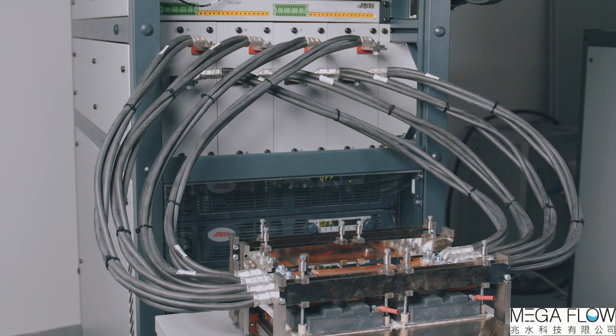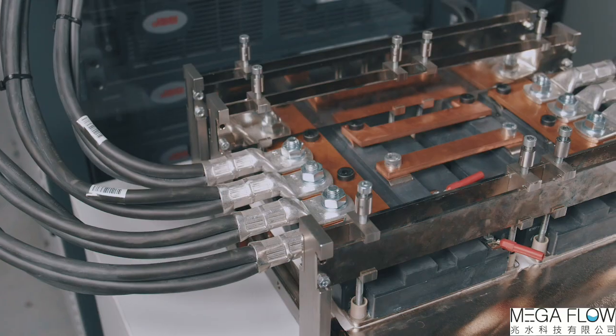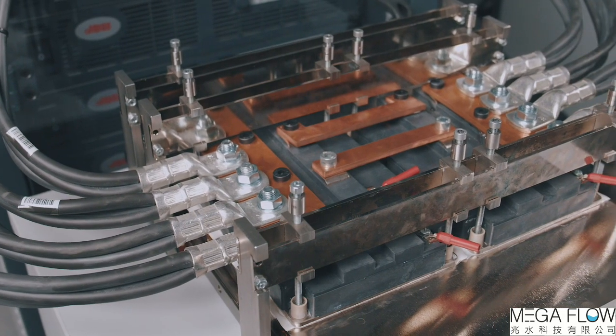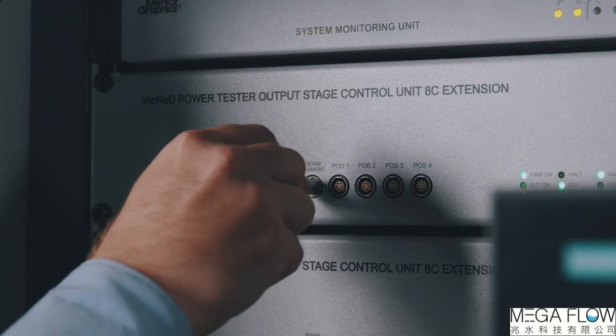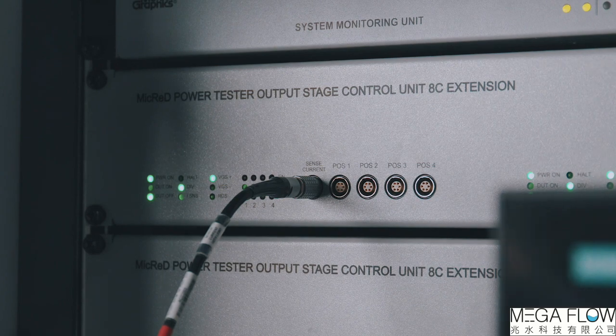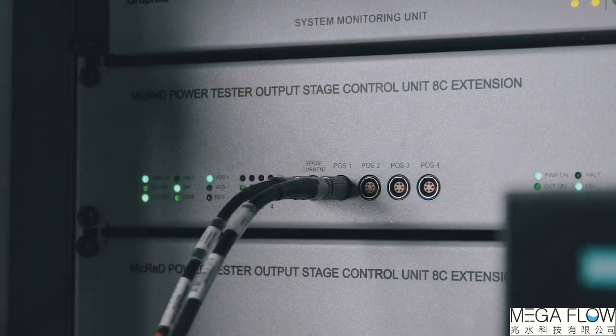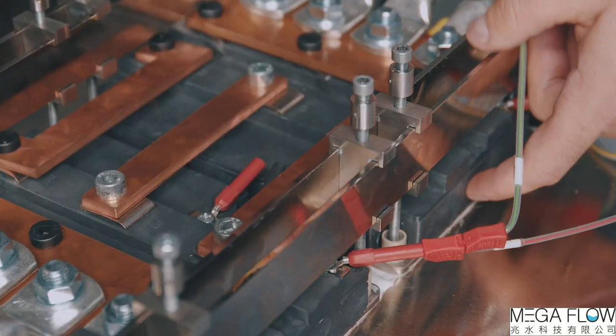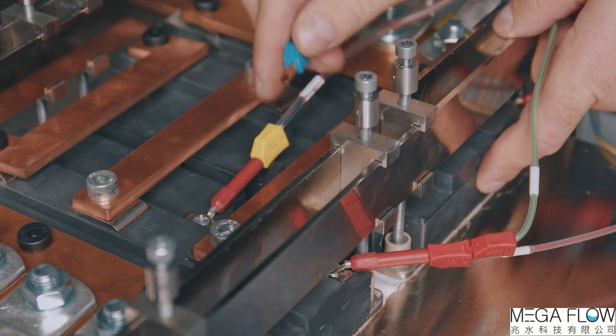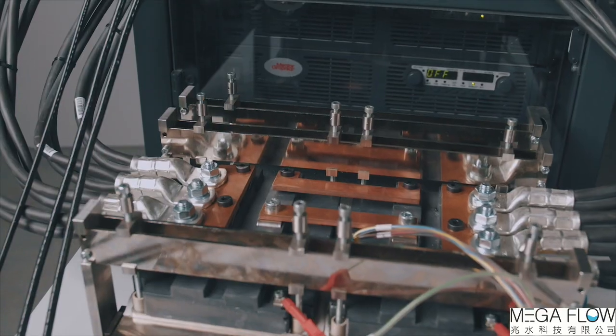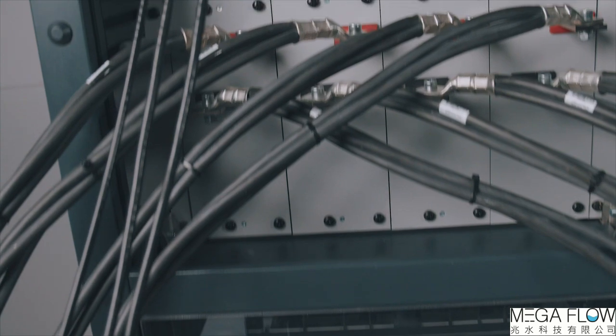The high current connections and measurement current cables need to be attached to the top and bottom of the device chains. Gate drive outputs and voltage measurement inputs are combined in a single connector to facilitate clean and simple wiring. The color coding of the banana plugs and the labels on the cable ends help in the connections. No other connections like thermocouple or other temperature sensors are needed for the junction temperature measurement.